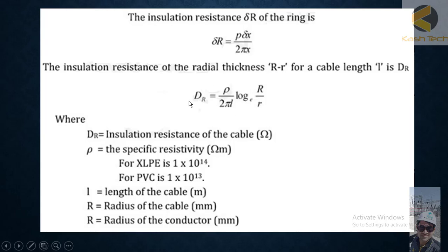You should know what parameters: the specific resistivity in ohm meters. For example, for XLPE cable is 1 × 10^14, and for PVC is 1 × 10^13. The length of cable, which you can easily find out. The radius of the cable, which also we can find out. The radius of the conductor, you can find out.